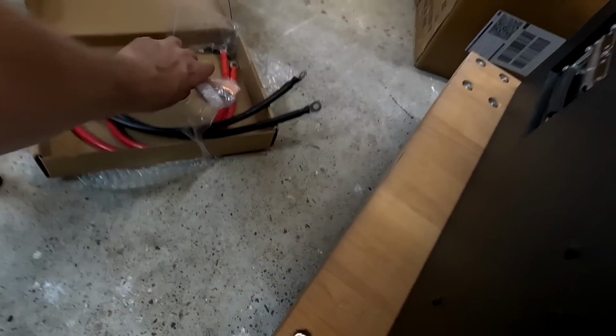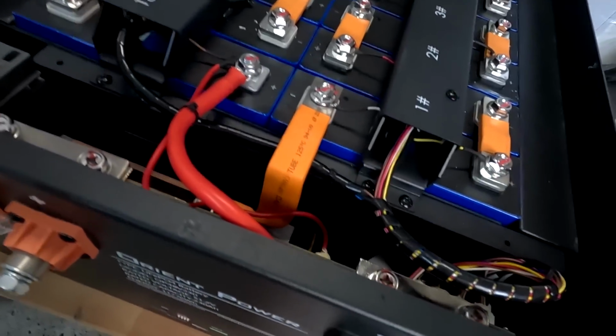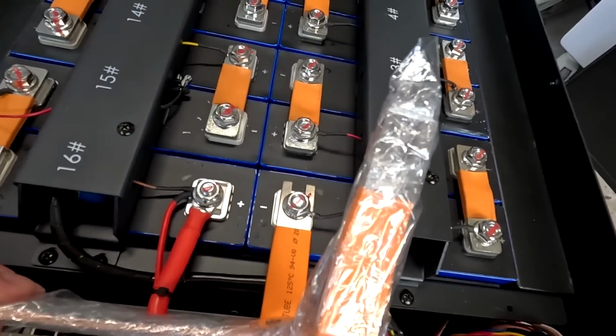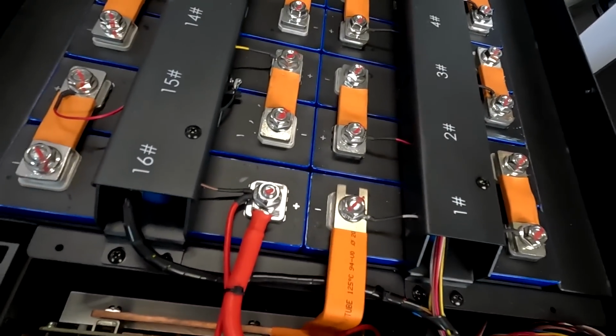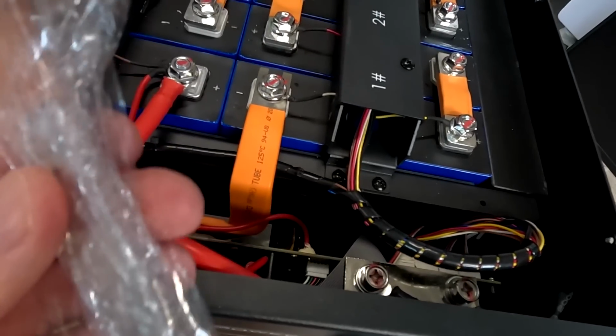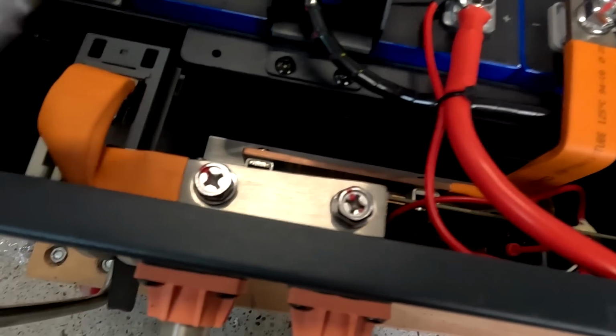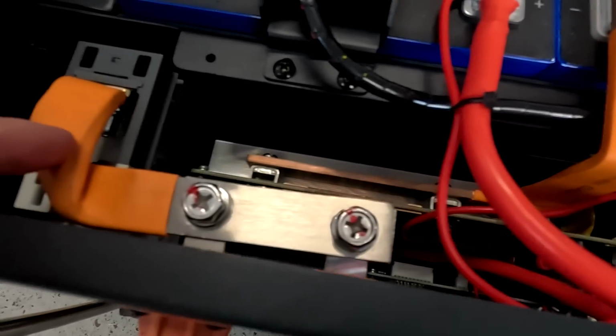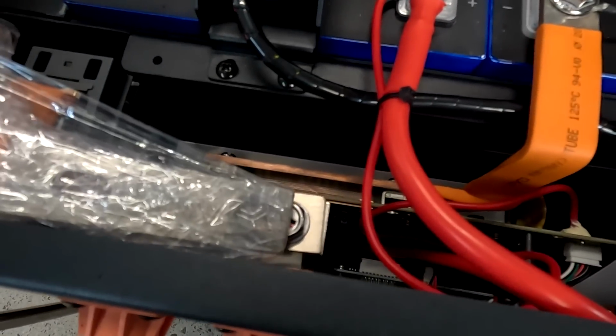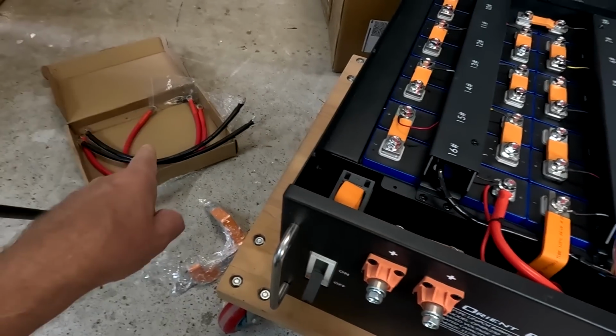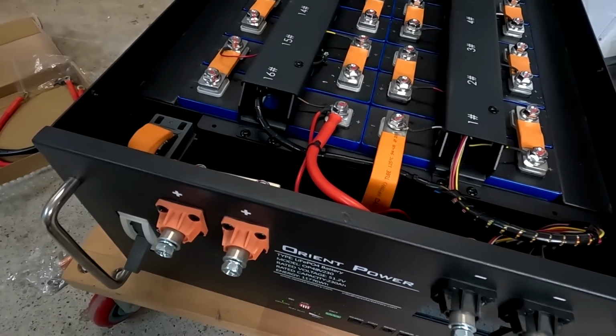I think we actually don't need the bus bars because we already have these ones. I'm sure this is the one coming from the BMS and going up to the main negative of the battery - yeah, we don't need that. And this one here, ah, that is the replacement - that is the bus bar for the circuit breaker. Okay, we have this already, so we only need to replace these cables. That should be very straightforward.